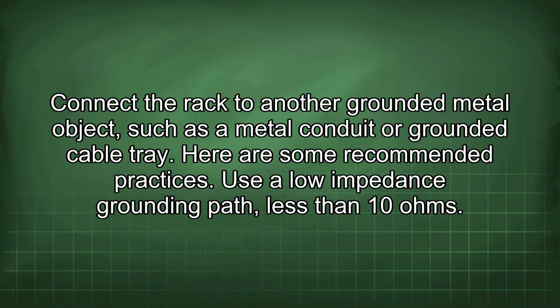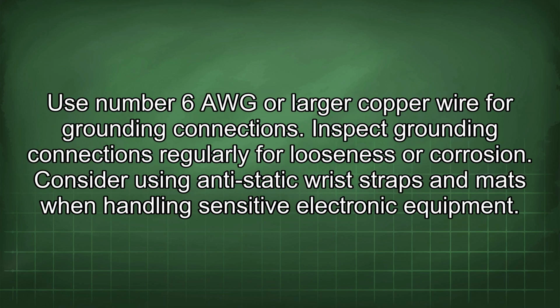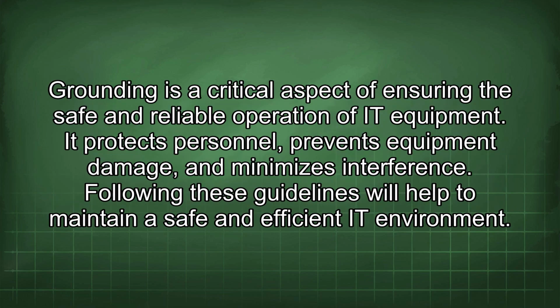Here are some recommended practices. Use a low impedance grounding path, less than 10 ohms. Use number 6 AWG or larger copper wire for grounding connections. Inspect grounding connections regularly for looseness or corrosion. Consider using anti-static wrist straps and mats when handling sensitive electronic equipment. Grounding is a critical aspect of ensuring the safe and reliable operation of IT equipment. It protects personnel, prevents equipment damage, and minimizes interference. Following these guidelines will help to maintain a safe and efficient IT environment.